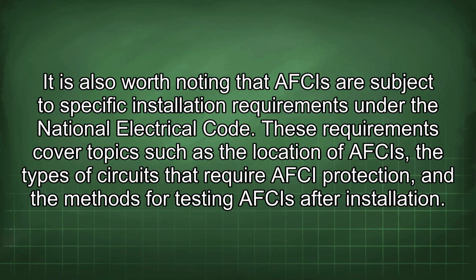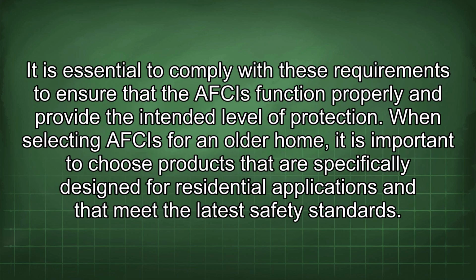It is also worth noting that AFCIs are subject to specific installation requirements under the National Electrical Code. These requirements cover topics such as the location of AFCIs, the types of circuits that require AFCI protection, and the methods for testing AFCIs after installation. It is essential to comply with these requirements to ensure that the AFCIs function properly and provide the intended level of protection.